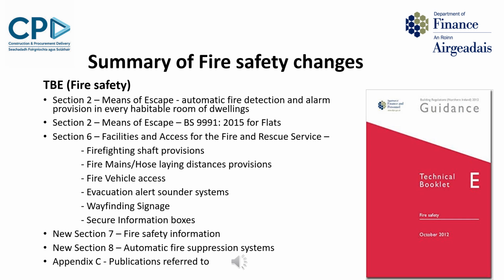With regard to Technical Booklet E, in Section 2, Means of Escape, the standard for automatic fire detection and alarm provision in dwelling houses and flats has been amended to require smoke alarms in every habitable room. Also for Means of Escape provisions for flats, the design standard BS 9991 of 2015 is now referenced. In Section 6, Facilities and Access for the Fire and Rescue Service, there are amendments in relation to firefighting shaft provision, fire mains and hose line distance provisions, and fire vehicle access distances. There are also new provisions for evacuation alert sounder systems, wayfinding signage, and secure information boxes, all in buildings containing flats with a top storey more than 11 metres above ground level.